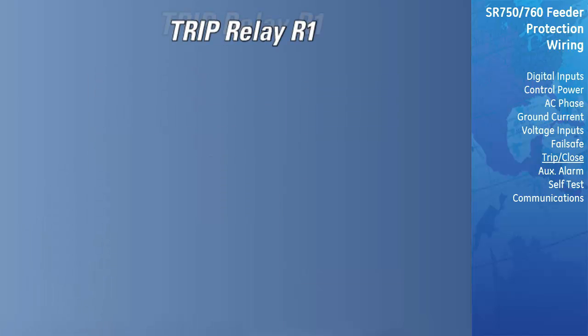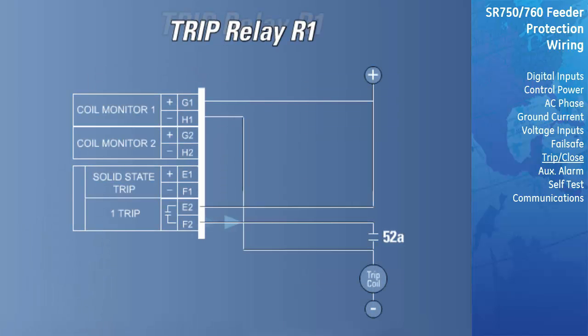This relay has dedicated trip and close contacts. These contacts will only operate when the relay issues a trip or a close command and cannot be programmed to operate at any other time. The trip contact, R1, is intended to be used as the main trip contact. It should be wired such that the breaker is opened when conditions warrant.